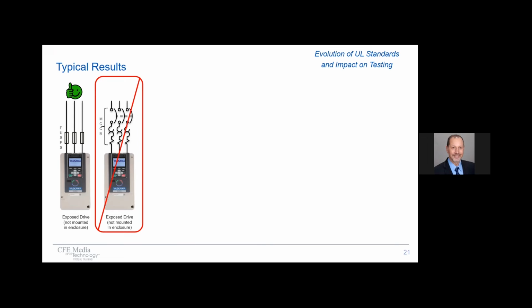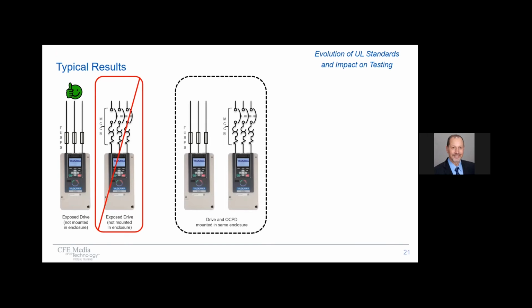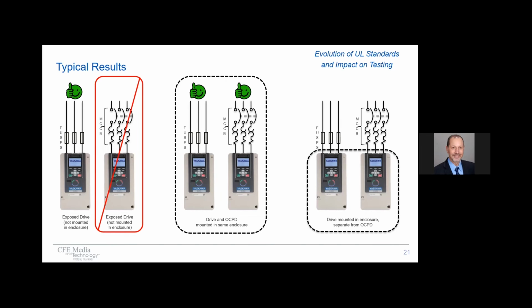Now let's consider those same kinds of protection, but with a supplemental enclosure. In other words, the drives are mounted inside of an enclosure. In that case, both fuses and circuit breaker by itself actually passes the test. It's often considered approved UL type of protection. And lastly, let's talk about a variation of that in which the drives are mounted in an enclosure, but those protective devices are mounted somewhere else. And it's very similar that both of those situations pass the test. There's one exception, however, with UL, and that is if the fuses being used are semiconductor type fuses, UL requires that they actually be located in the same enclosure as the drive. So that's just one caveat there.